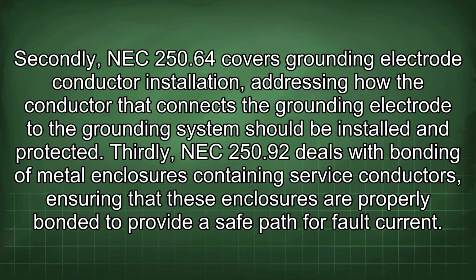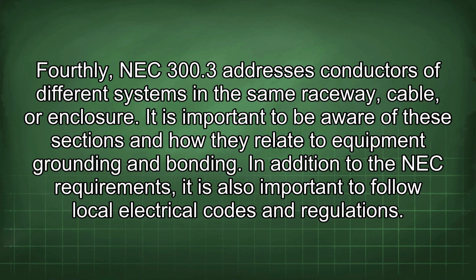Thirdly, NEC 250.92 deals with bonding of metal enclosures containing service conductors, ensuring that these enclosures are properly bonded to provide a safe path for fault current. Fourthly, NEC 300.3 addresses conductors of different systems in the same raceway, cable, or enclosure. It is important to be aware of these sections and how they relate to equipment grounding and bonding.